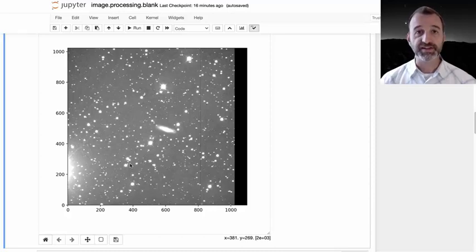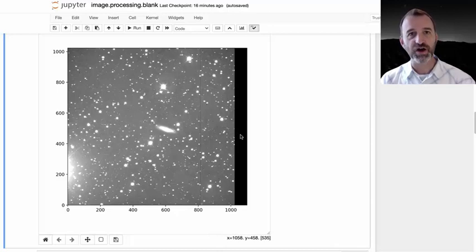All right, the detector we have here is actually a 2K by 2K chip. That means it's 2048 pixels by 2048. But you'll notice we have it binned 2 by 2, which means we're going from 0 to 1023 and 0 to 1023 here. But if you look carefully, you'll notice there are a few extra columns here.